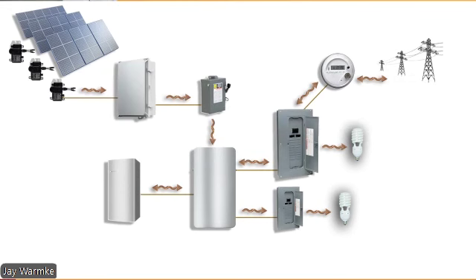And the Enphase system, battery banks within these systems, especially with lithium ion, are not just batteries, right? They have battery management systems, charge controlling systems, and in this case, they have small inverters, microinverters built into that battery bank. So your switch is feeding into these microinverters, and they're then converting that to DC for the battery, and then taking from the battery and converting to AC. It then feeds into the smart switch and goes to the critical load panel.